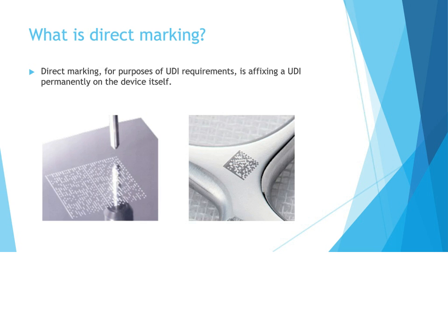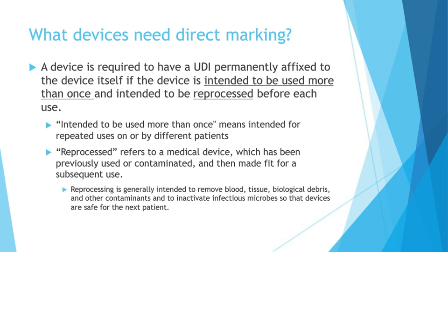So what devices need direct marking? It is really important you review this document before you move forward and start etching the UDI all over your device. It really is intended only for devices that will be used more than once and that will be reprocessed before each use. So I've included FDA's definition of both these requirements here, as well as their understanding of the word reprocessing.